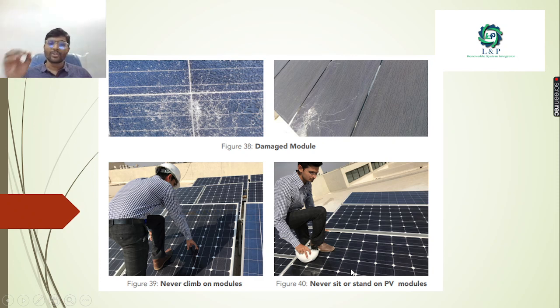Then, most importantly, there is a possibility for the module to get damaged when people are playing cricket, or if somebody is doing blasting operations. There is a possibility for stones to damage the PV modules. And some people sometimes walk over the modules. We should never climb on the modules. Never sit or stand on the PV modules.